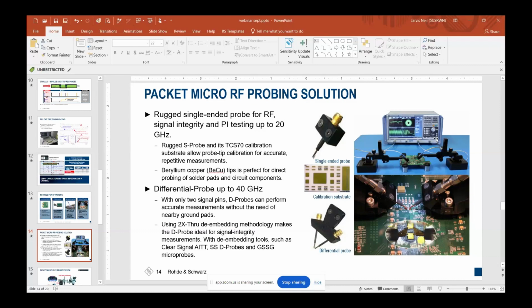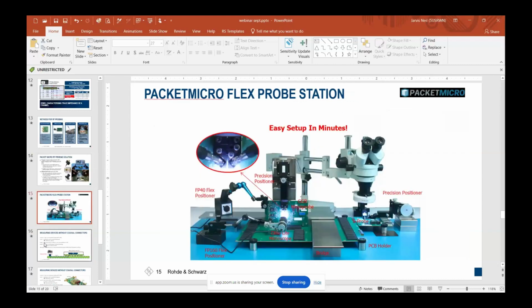They have single-ended and differential probes, and they're not the only manufacturer, by the way. And you'll have a microscope also. The microscope shows you the fine pitch and what's going on, where I can manipulate the probes. You have to planarize them, get them flat, and then you can measure things. They have probes up to 67 gig. I know there's another guy that has stuff up to 110, so it's certainly possible. Obviously, the higher in frequency, the more considerations you need to make. But anyway, that's what a whole probe system might look like.